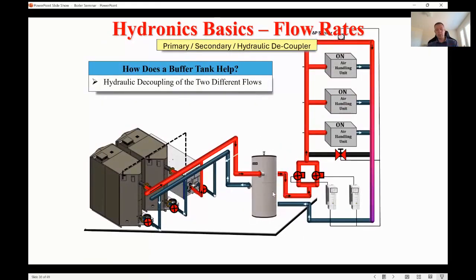So one of the solutions to that is putting a buffer tank in. With a buffer tank, you'll have a big amount of thermal mass there, and it's not going to be as prone to that short cycling, if you will, that you'll see in a standard primary, secondary situation. But there's other ways you can handle this as well. What I like about buffer tanks is it adds mass to the system as well. You may or may not need it, but being a boiler guy, anytime I can promote longer run times is awesome to me.